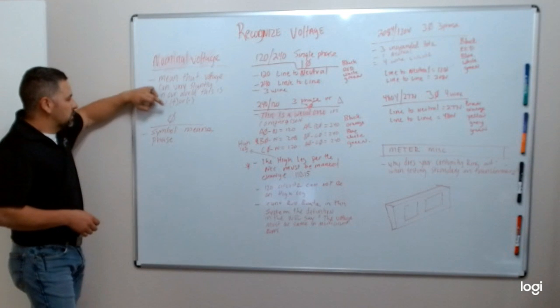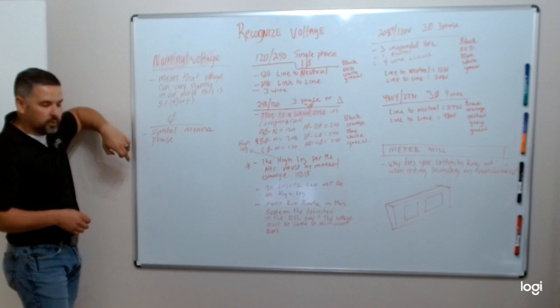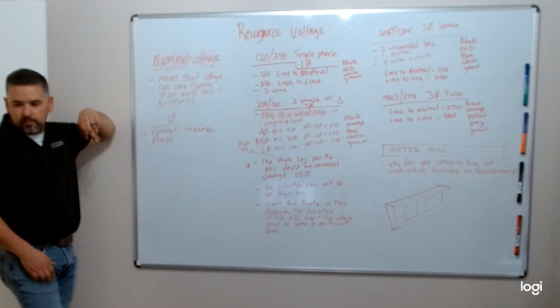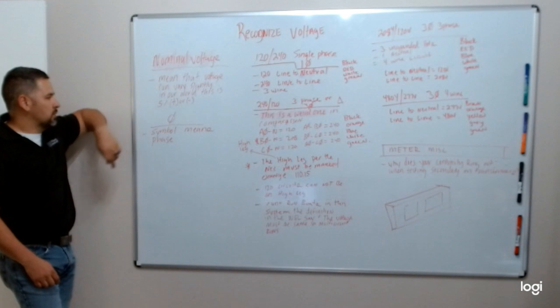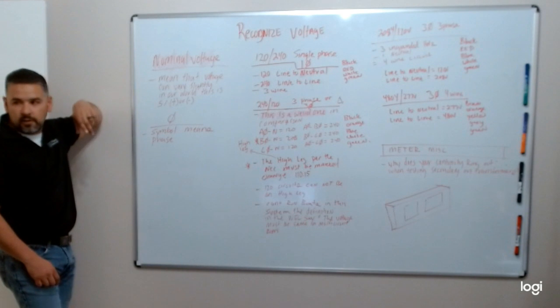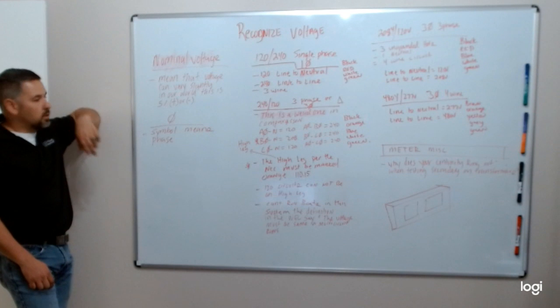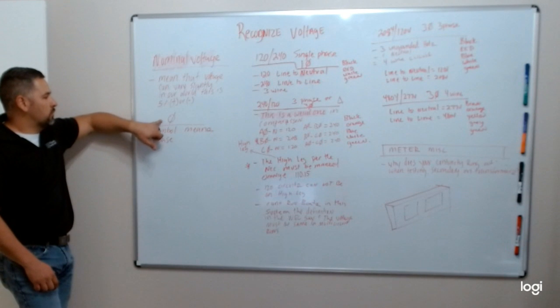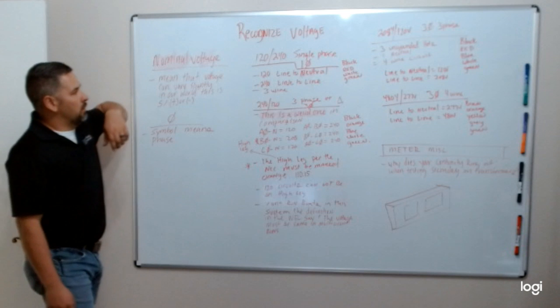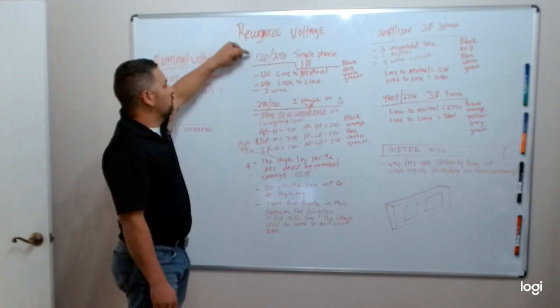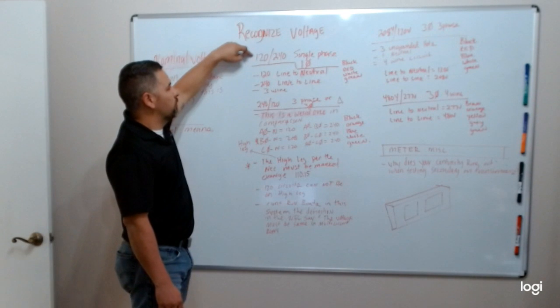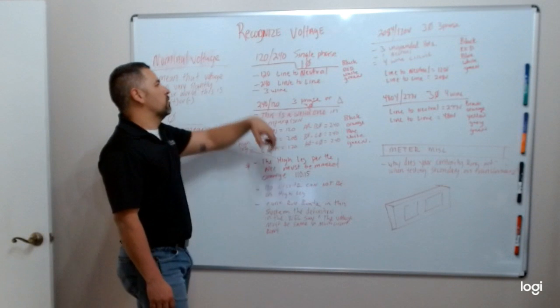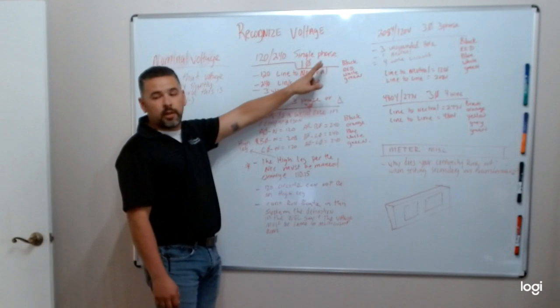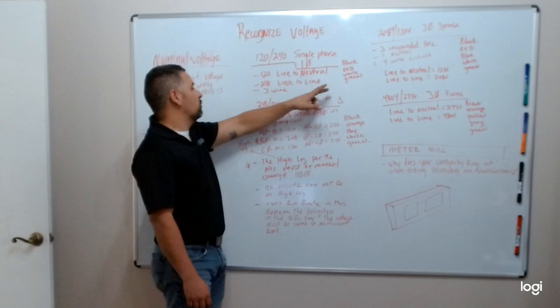You'll see this little circle with a cross through it. That is going to be your phase. So if it's a three-phase, single phase, you'll have that little symbol. The first set that we're going to be going through is 120, 240 single phase. Your normal coloring for that is going to be black, red, white, green.